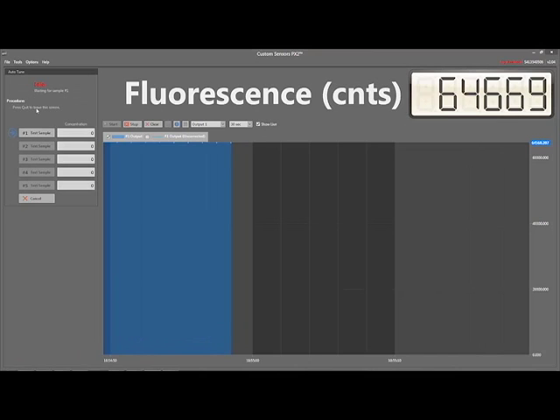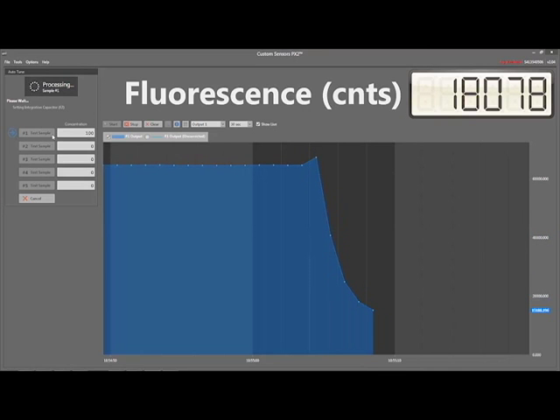I am now prompted to submerge my probe in the highest sample, which I've already done, and enter in my highest concentration. My full-scale sample is 100 ppm, so I will enter the number 100 into the box, and then select number 1 test sample. The PX2 will adjust its settings automatically. This may take up to 1 minute to complete. Once the optimal settings have been selected, the unit will take 15 measurements, which are used to determine the full-scale calibration point.